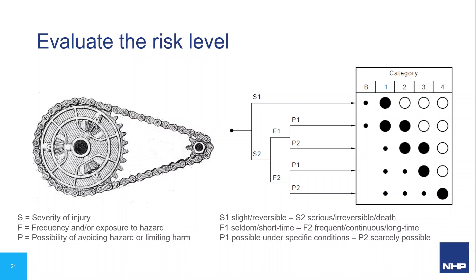Let's look at this chain and sprocket example. We start at the left of the chart and move right, making decisions at each junction. The first junction is S — severity of injury. The sprocket teeth are large and sharp enough to take your finger off. A bruise or scratch requiring first aid is S1 (slight). Anything requiring an ambulance or emergency room visit constitutes S2 (serious). Removal of a finger? S2 it is.